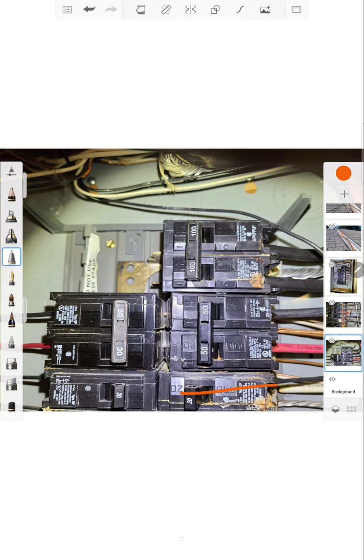But we can already see damage like this too, where this 50 amp circuit breaker that's supplying power to a range is actually not seated, and you can see corrosion behind it. Things like this create a poor connection, and poor connections create heat, and we don't want heat in an electrical panel.